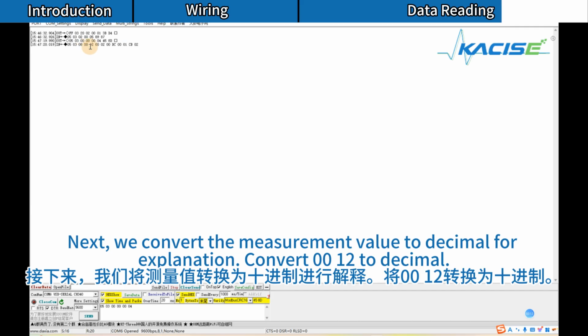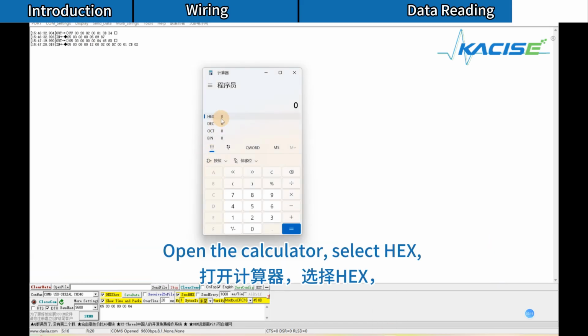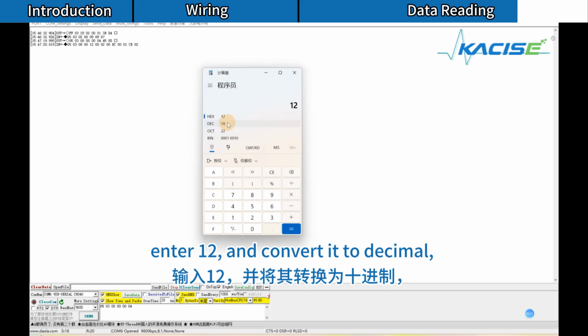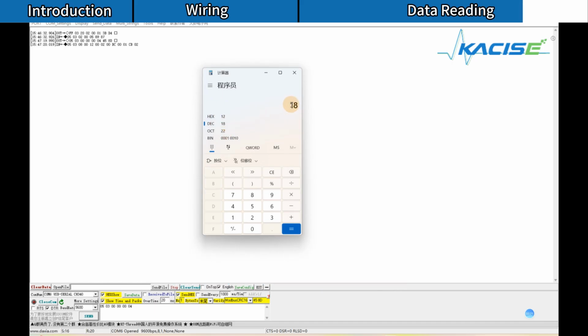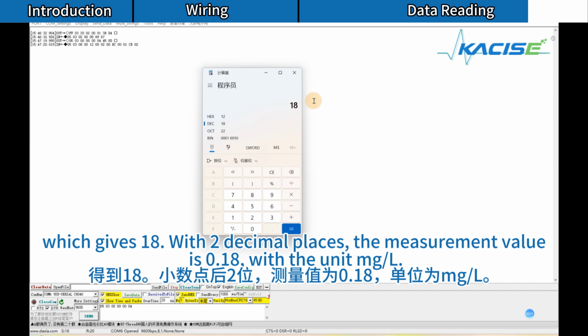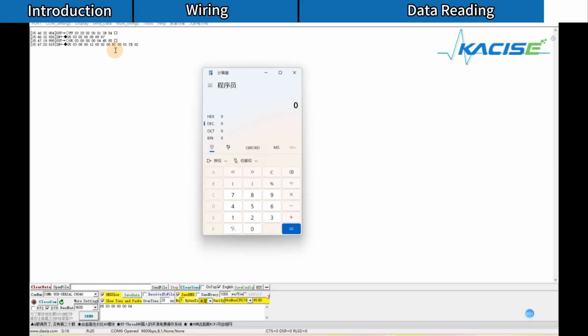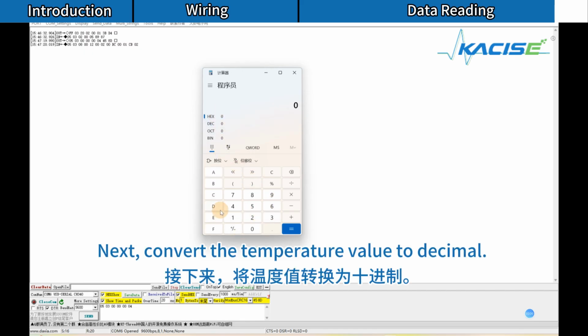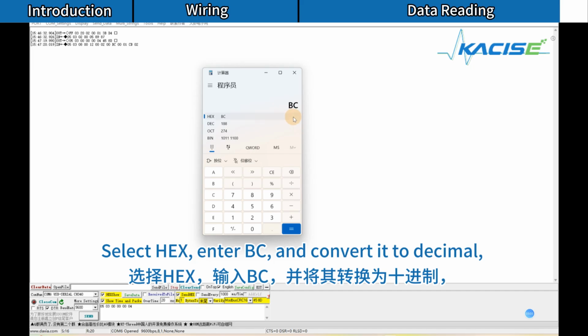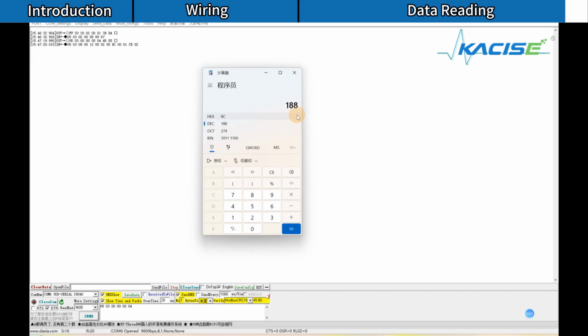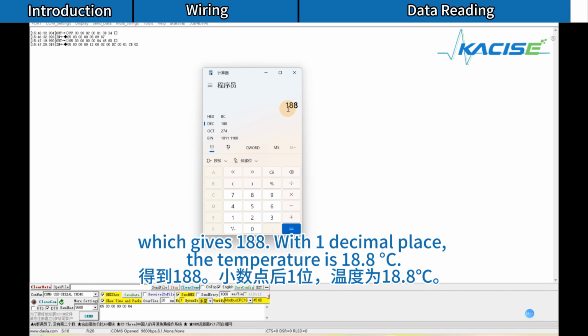Next, we convert the measurement value to decimal for explanation. Convert 0012 to decimal. Open the calculator, select HEX, enter 12, and convert it to decimal, which gives 18. With 2 decimal places, the measurement value is 0.18, with the unit mg/L. Next, convert the temperature value to decimal. Select HEX, enter BC, and convert it to decimal, which gives 188. With 1 decimal place, the temperature is 18.8 degrees Celsius.